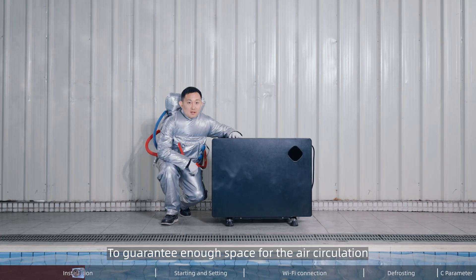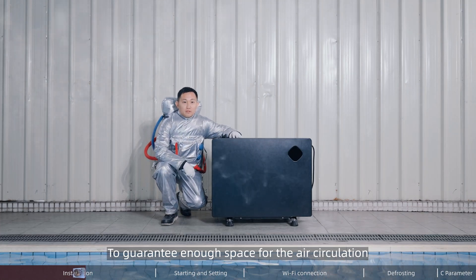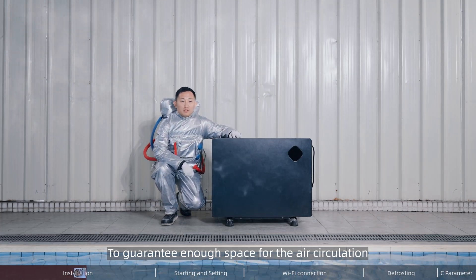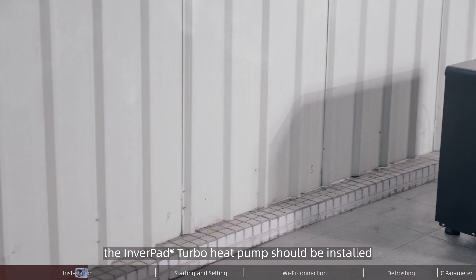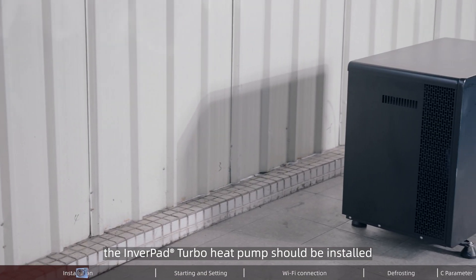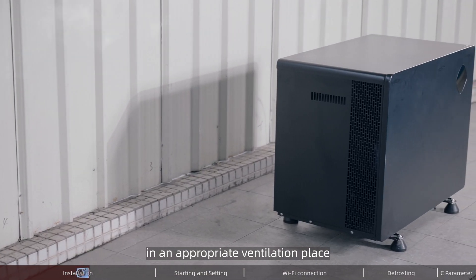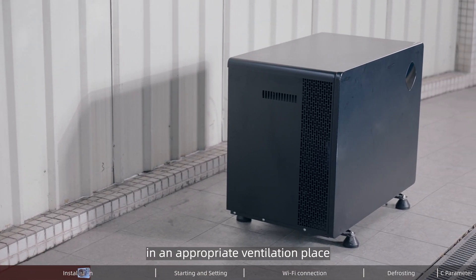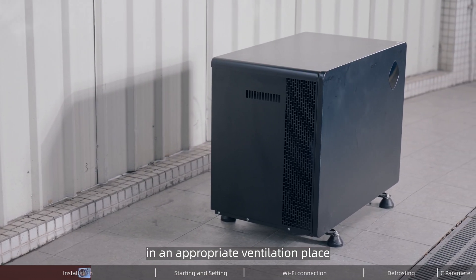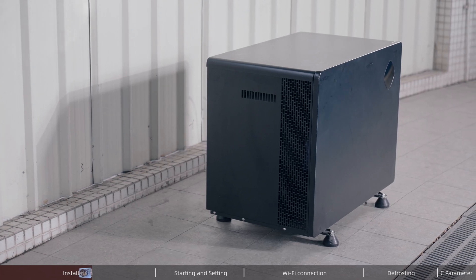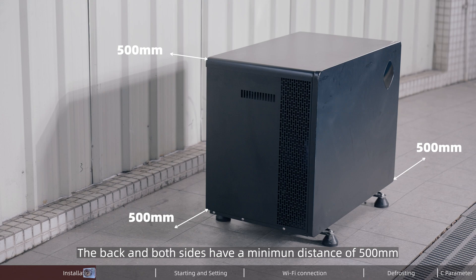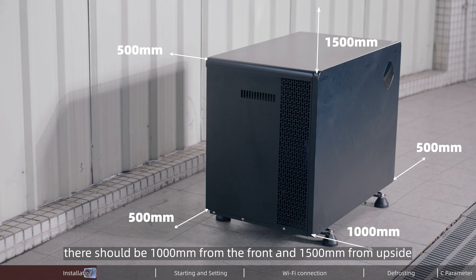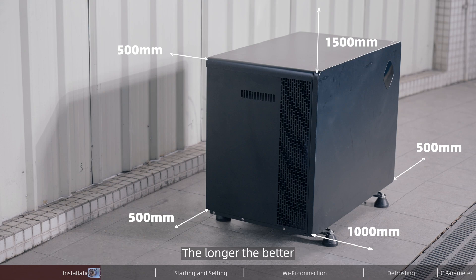To guarantee enough space for air circulation, the Inverpad heat pump should be installed in an appropriate ventilation place. The back and both sides have a minimum distance of 0.5 meters. There should be 1 meter from the front and 1.5 meters from the upside. The longer the better.